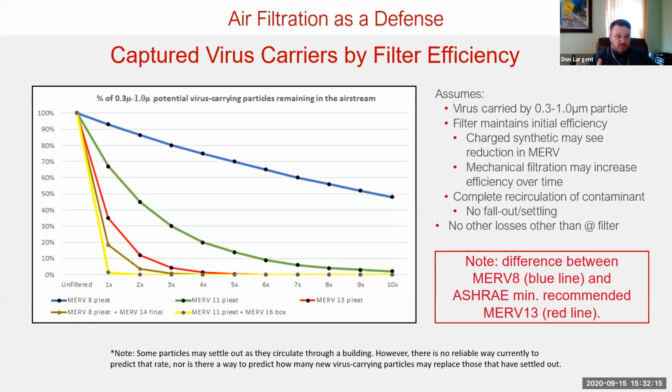So something that's rated as a MERV 13, if it's a purely synthetic media, which has an induced charge, that charge can be rendered ineffective during normal operation and actually reduce its MERV rating from a MERV 13 to maybe a MERV 11 or MERV 10 or even lower. So in your most critical applications, such as hospitals, pure mechanical filtration is what is recommended.